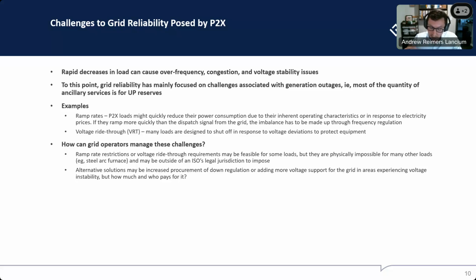Or there could be a voltage instability event on the grid. The voltage drops generally, and the equipment is designed to shut the system off to protect the equipment, because it's not meant to operate under those low voltage conditions. Well, if that happens, now the load on the system has just decreased, and the system frequency goes up. It changes the power flow on the system, which could cause transmission overloads, all kinds of instability and reliability events that our current ancillary service suite is not really well suited to deal with.